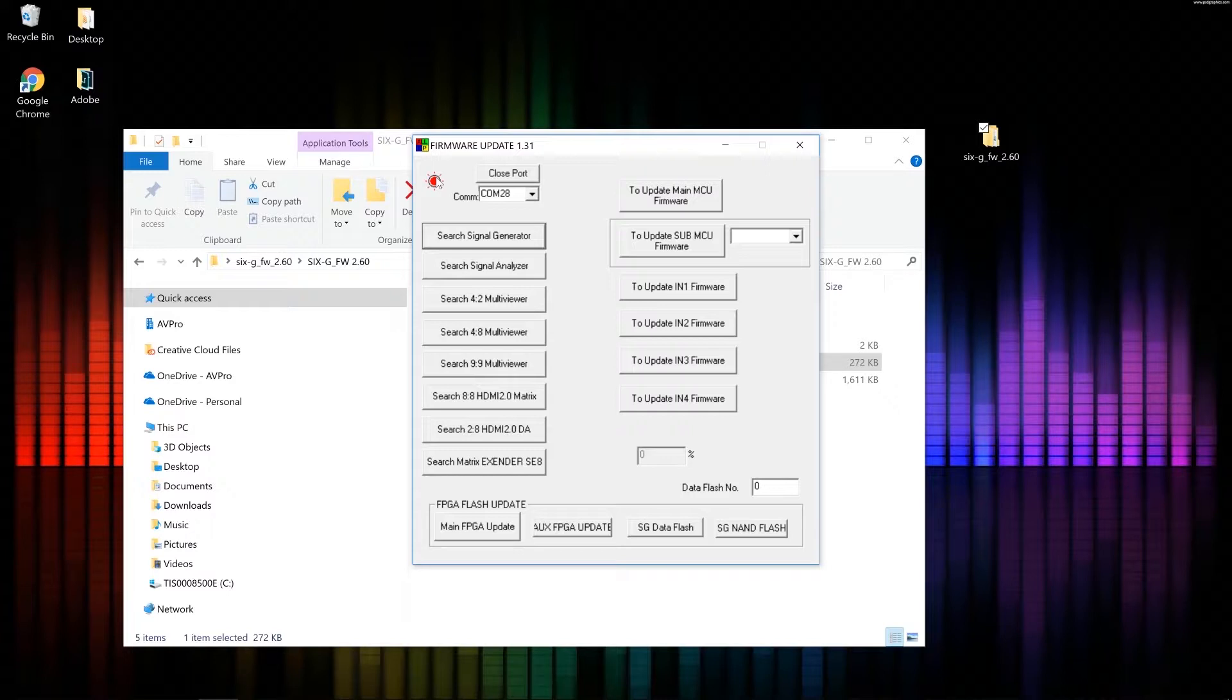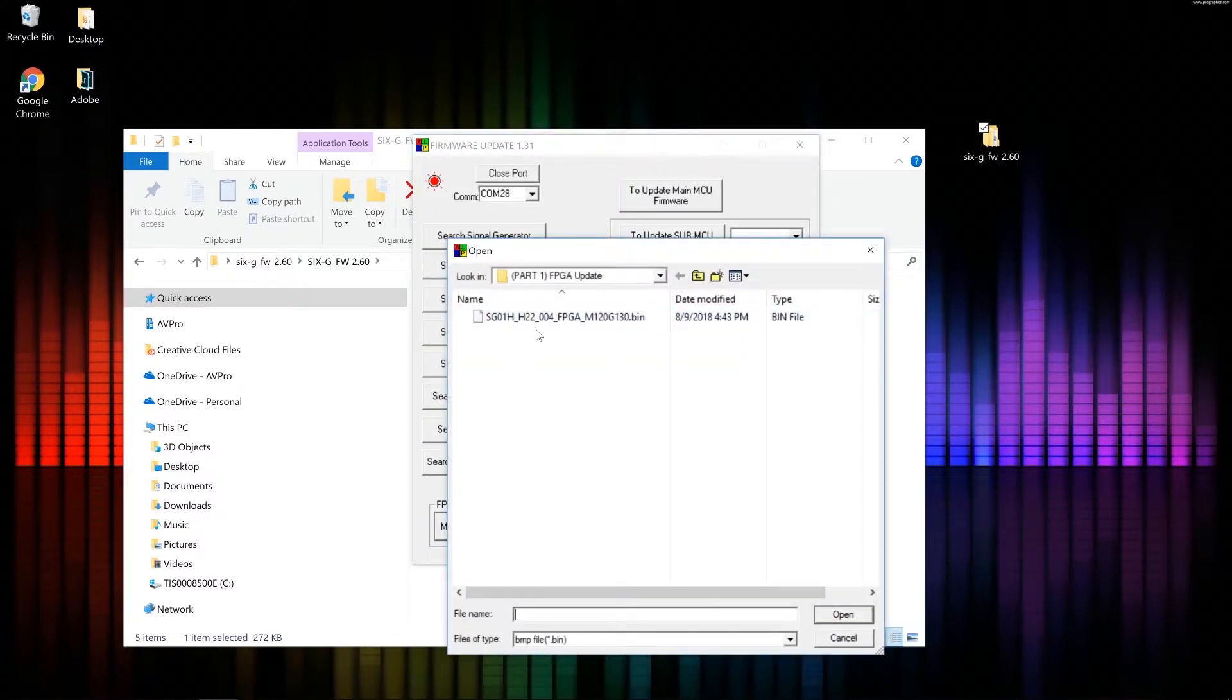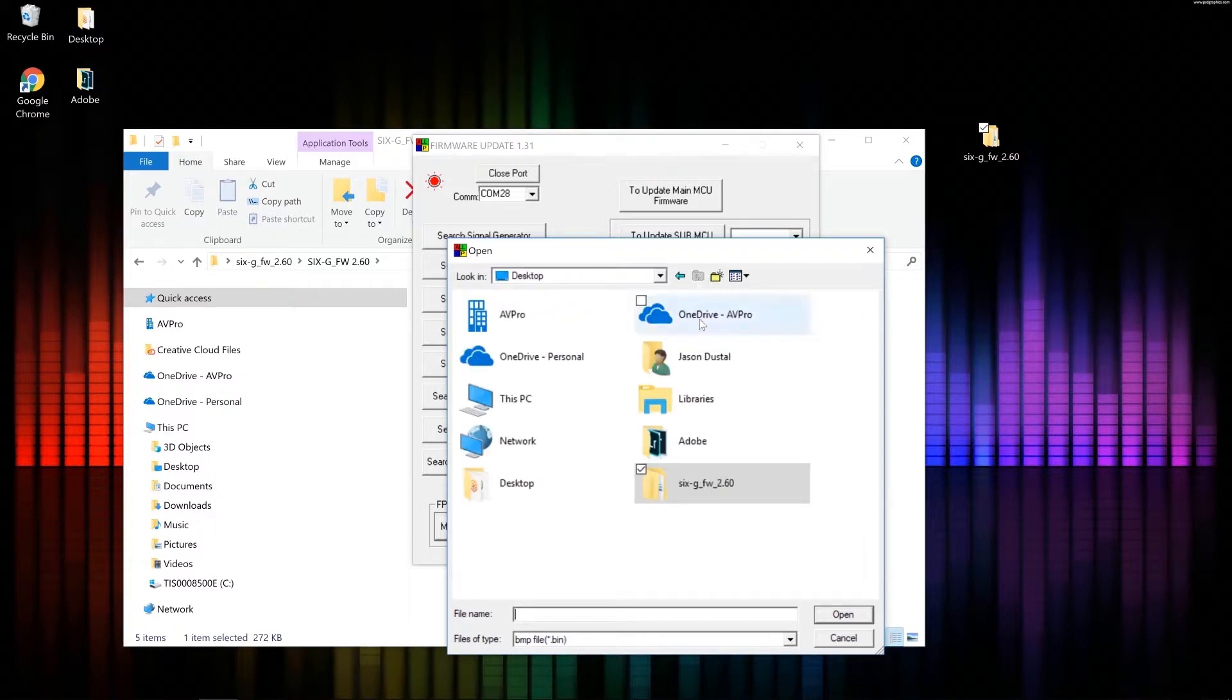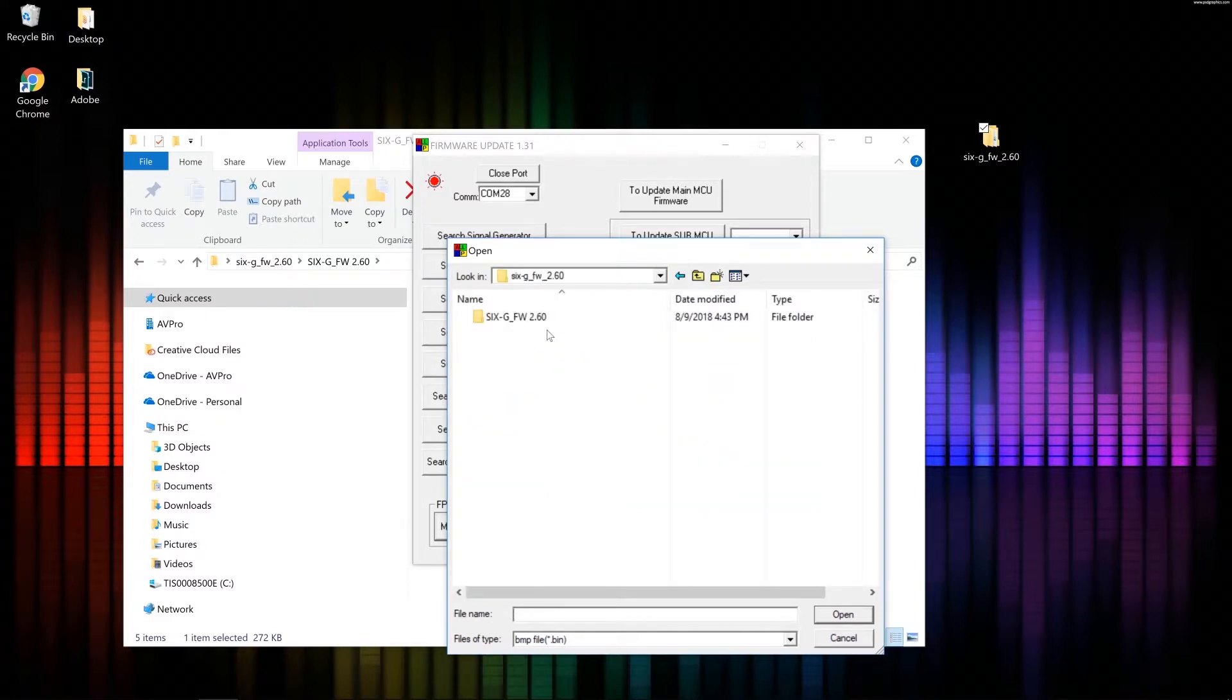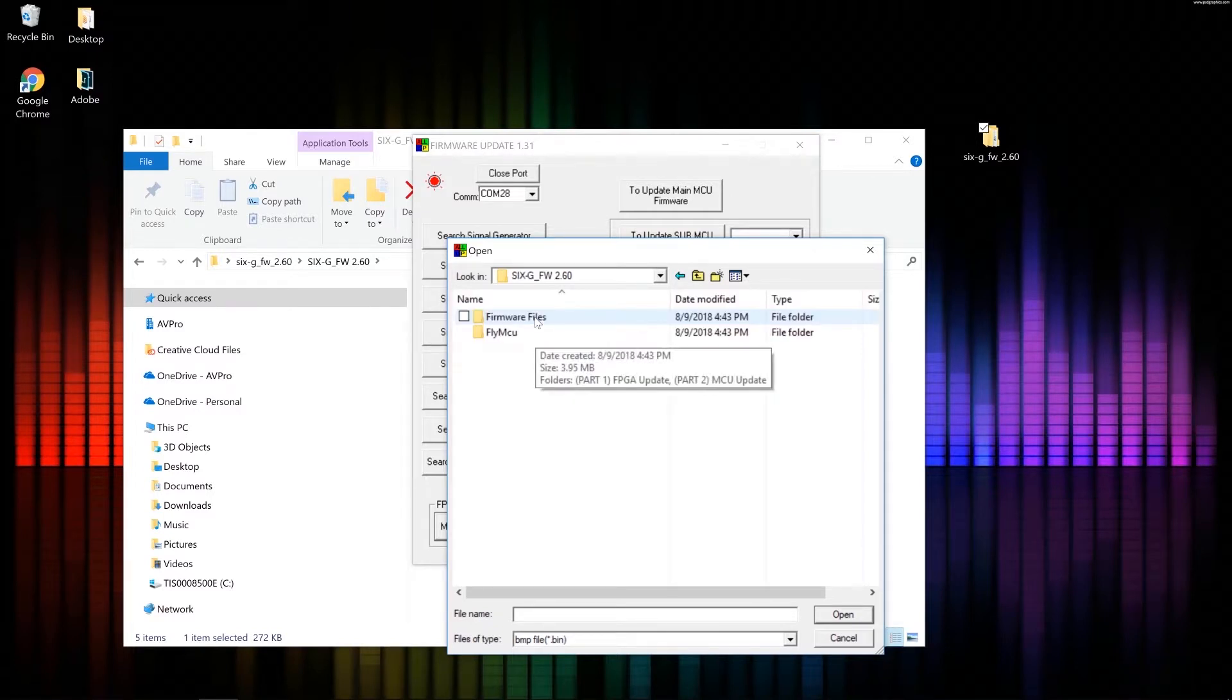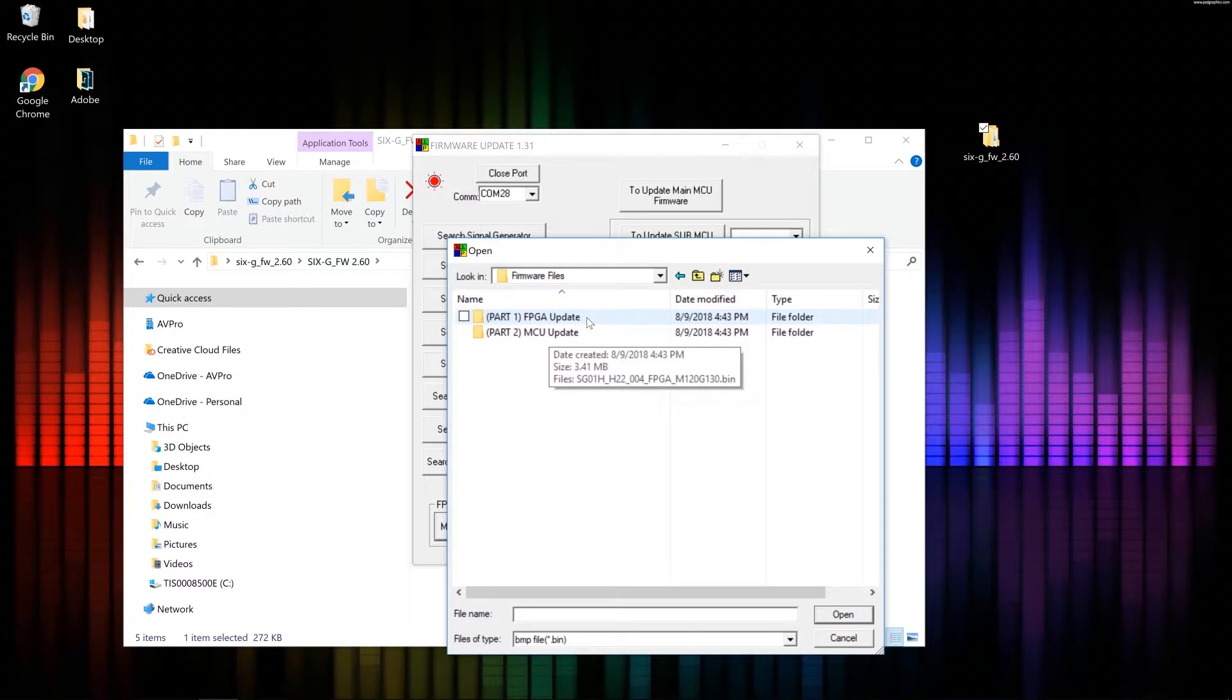The first part of the firmware update is the main FPGA update. So go ahead and click on that. Now I got lucky here because the file popped up right away. But if you do have to find it, go back to your desktop. This is why I put it on the desktop. Go to your desktop. Open up 2.60. Open up that folder. Open up firmware files. And this is the part 1 FPGA update. So open that.